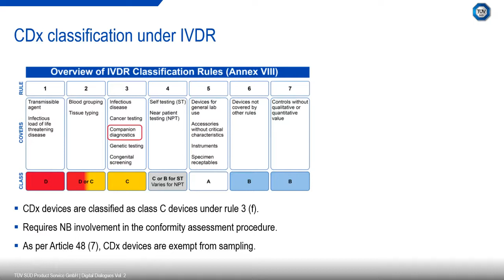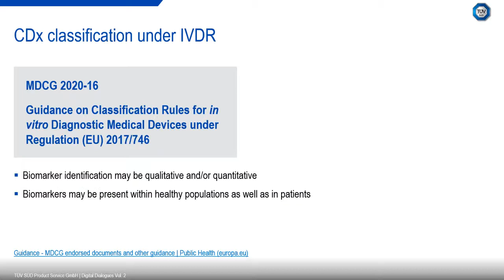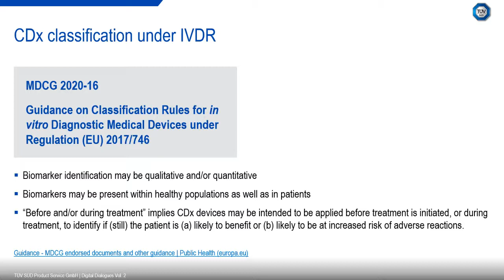The Medical Devices Coordination Group issued a guidance in general for classification for in vitro diagnostics, and this guidance is shown on the slide here, and the link is provided below. It was worthwhile just quickly reviewing what it states with regards to companion diagnostics. So this guidance specifically states with regards to CDX devices that biomarker identification may be qualitative and or quantitative in nature, that the biomarkers may be present within healthy populations as well as in patients. And the phrase in the definition in Article 2, before and or during treatment, implies that CDX devices may be intended to be applied before treatment is initiated or during treatment to identify if still A, the patient is likely to benefit, or B, likely to be at increased risk of adverse reactions. And as I say, the link is provided on this slide if you are interested in that particular guidance document.